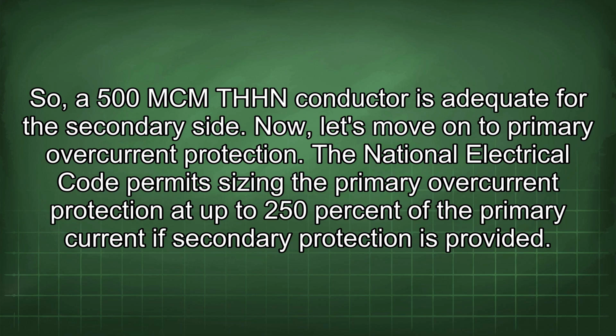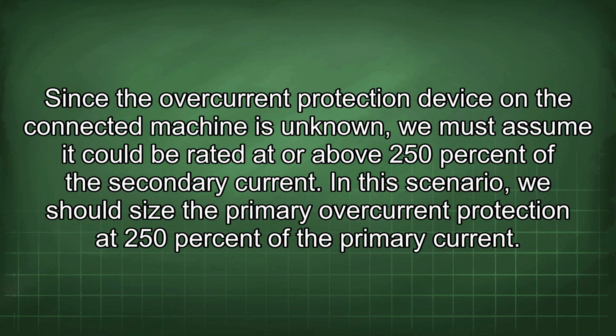Now let's move on to primary overcurrent protection. The National Electrical Code permits sizing the primary overcurrent protection at up to 250% of the primary current if secondary protection is provided. Since the overcurrent protection device on the connected machine is unknown, we must assume it could be rated at or above 250% of the secondary current. In this scenario, we should size the primary overcurrent protection at 250% of the primary current.